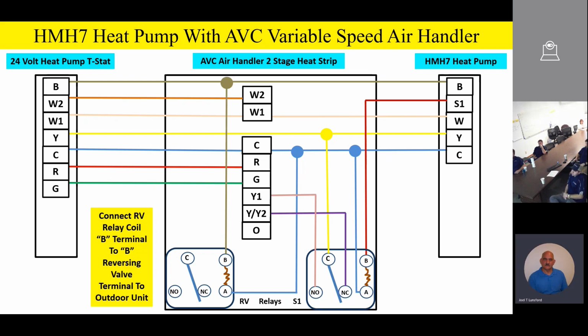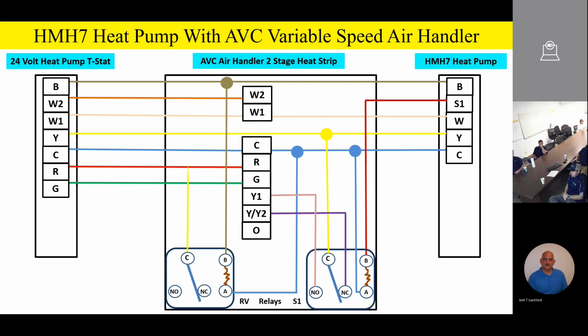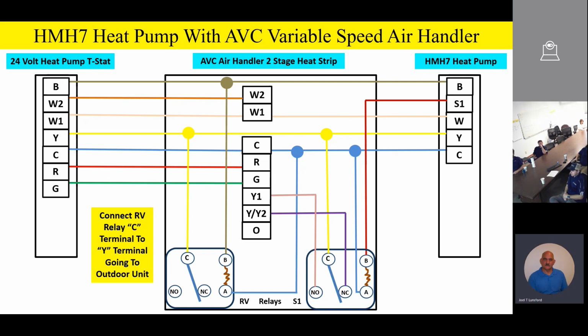The B terminal, and this is important, the B terminal on the RV relay is going to go up and hook up to the B wire going outside for reversing valve operation. Another way of thinking about that RV relay is we're going to energize that relay anytime we go into the heating mode of operation. The common terminal for the switching contacts on the RV relay is going to go up to Y as well. So anytime we have a call for compressor operation, both relays will be energized and ready to go to work. Now watch this, the normally closed contact on the RV relay is going to go to the O terminal.